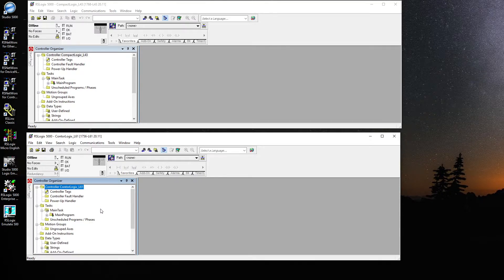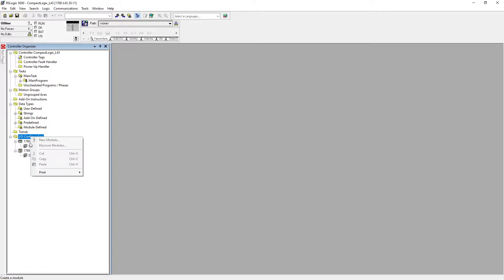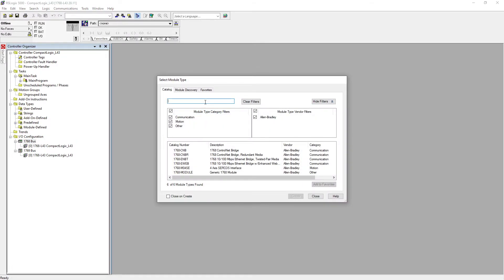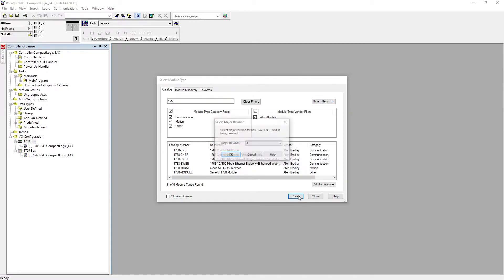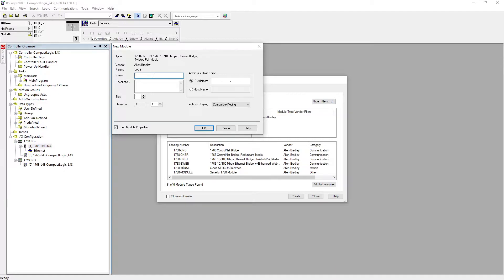Now what we're going to do first — let's select the CompactLogix and we need to add an ENBT card for the CompactLogix, from where we're going to communicate with other PLCs. It's going to be the 1768-ENBT — that's my CompactLogix Ethernet card. Hit create, revision is 4, and it's going to be 'CompactLogics ENBT,' slot number 1. The IP address is 192.168.1.22 — hit OK.